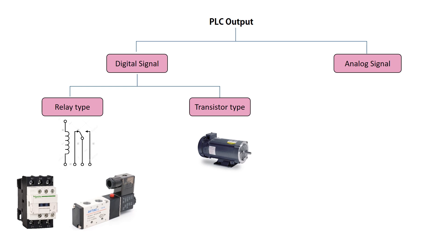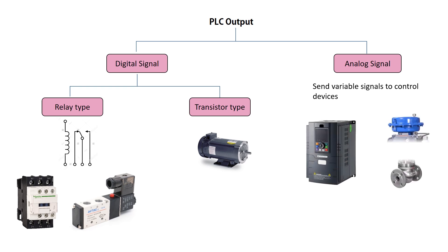PLC analog outputs are used to send variable signals to control devices that require a range of values rather than simple on-off states. These signals can be either voltage or current and are used to control devices that need precise adjustments. Examples of PLC analog output devices are variable frequency drives and control valves.